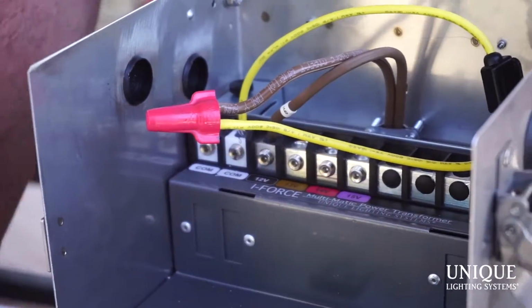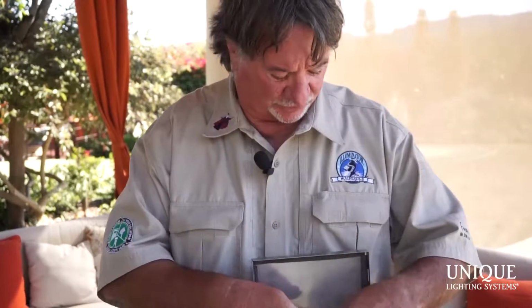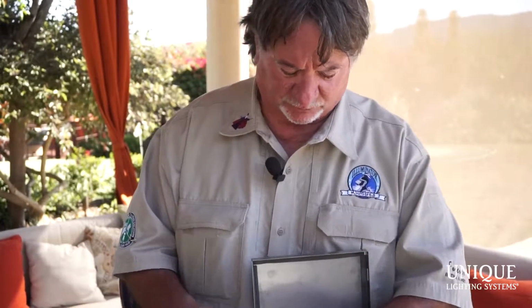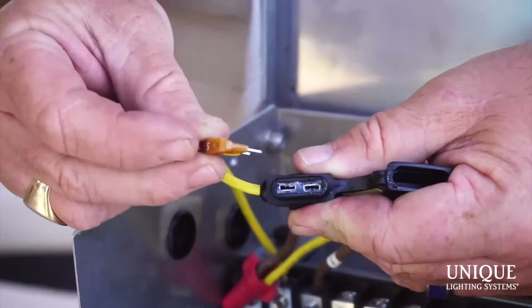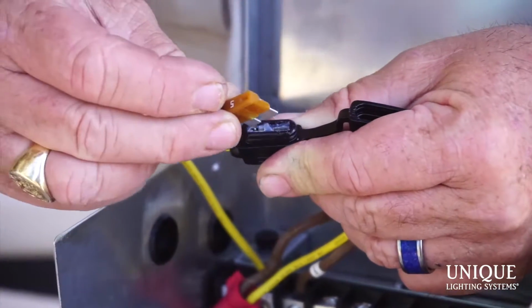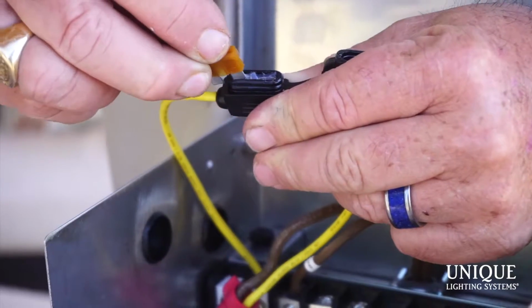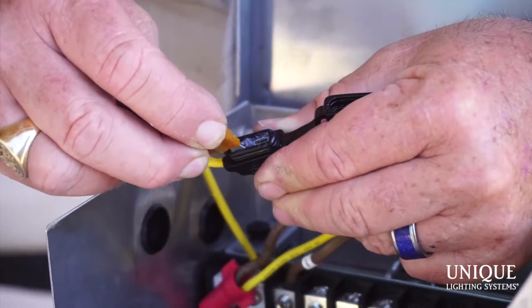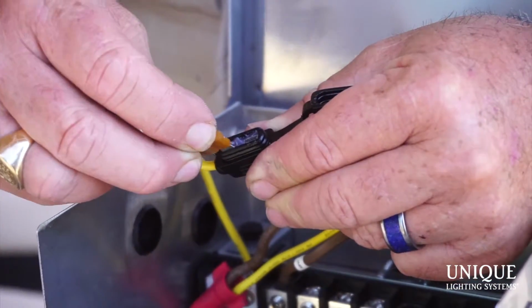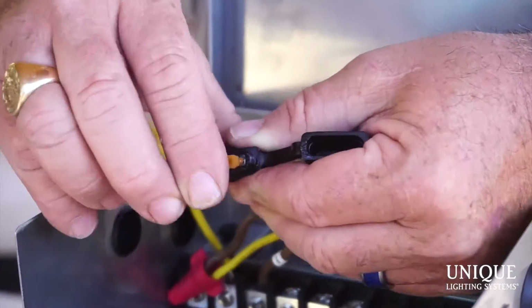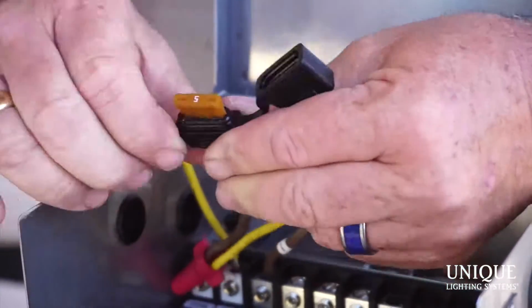Doesn't take long. Now what was our amperage? We look at our schedule - it was 1.6 amps. I grab a 5 amp fuse, put the 5 amp fuse in, and what you want to make sure with a fuse - all fuse holders are the same - is that this tab does not go on the back side of the female connector into the rubber insulation. Make sure you're going right into the mechanical part of it. Get in there tight, make sure there's lots of grease in there, and that baby is ready to go.